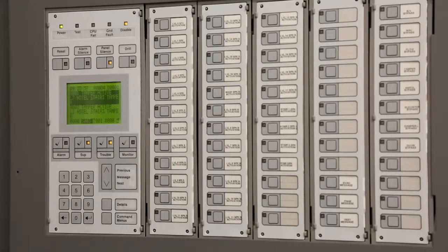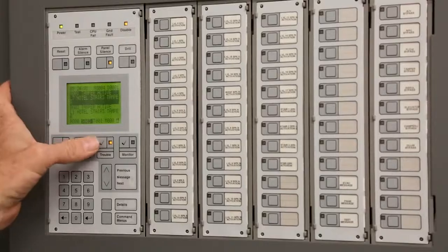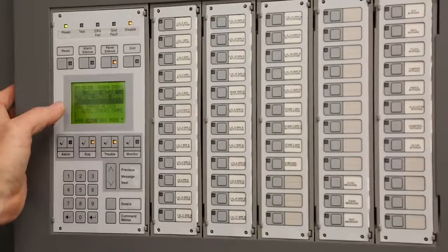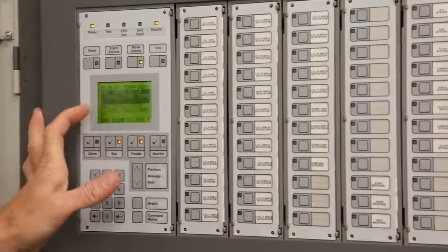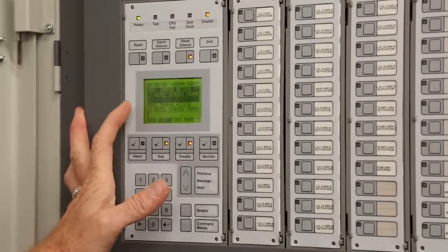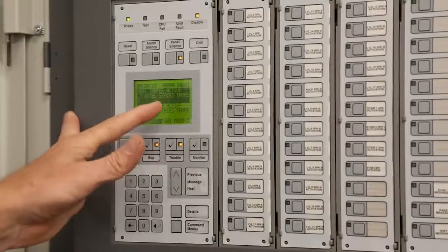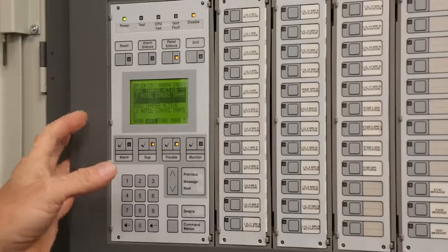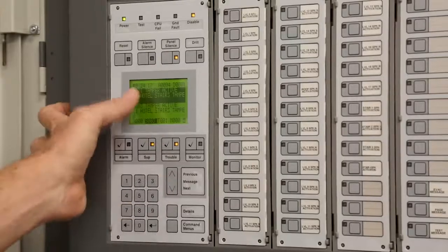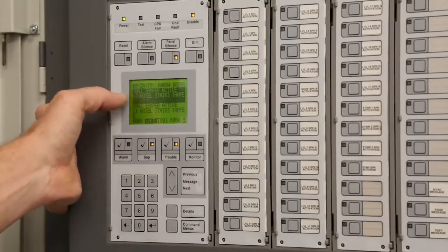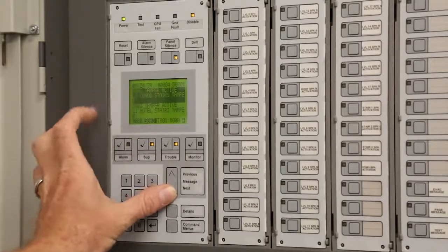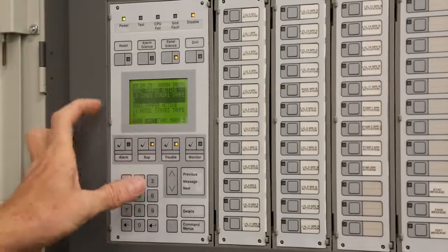Right now, for instance, like I said, we already talked about the trouble with supervisories. Right now, they have a couple valves shut, and it will actually tell you that it's a tamper active. So basically the control valve for the level 7 hotel stair 3 tampers, it's closed right now. They have an issue with it. You can scroll up and down. The first one always comes up right there. You can scroll down, that's your second. Obviously you have 3 right now, that's your second one.